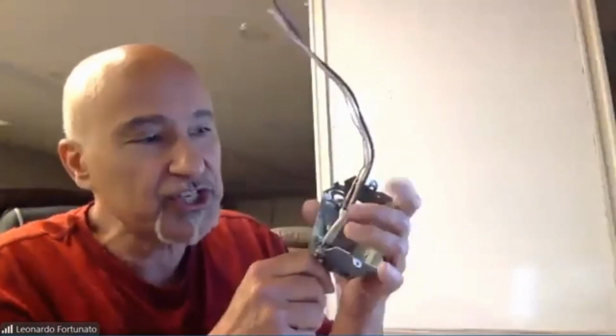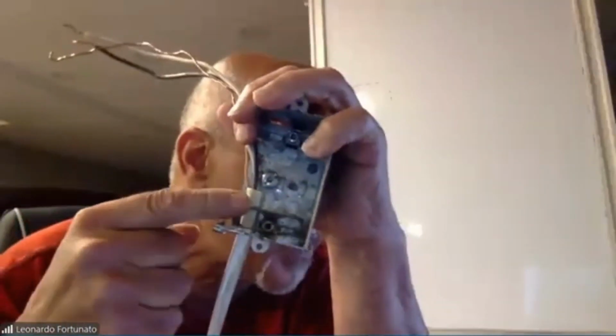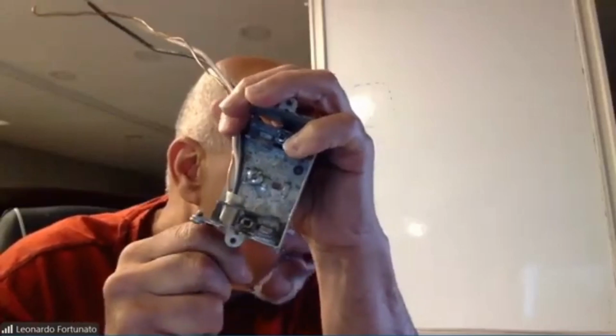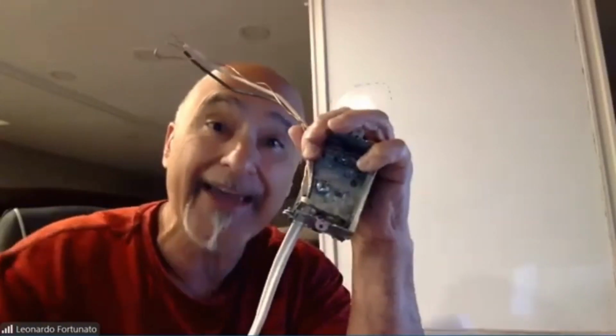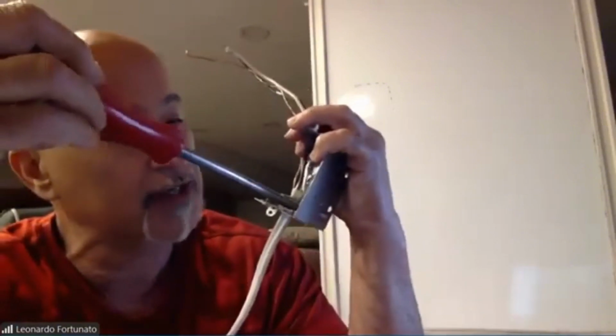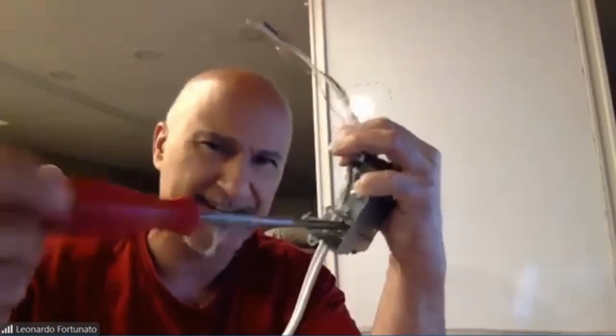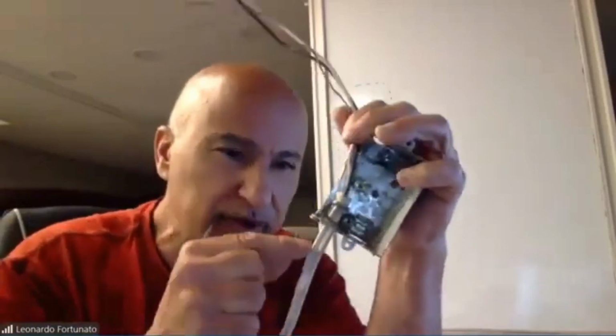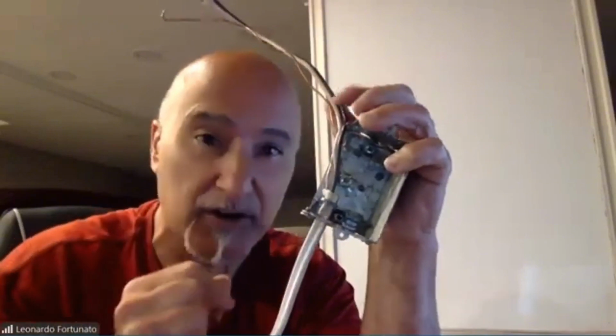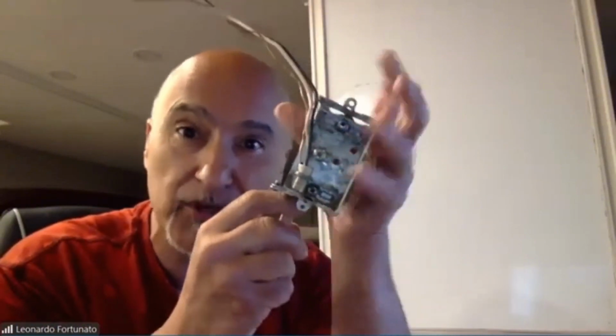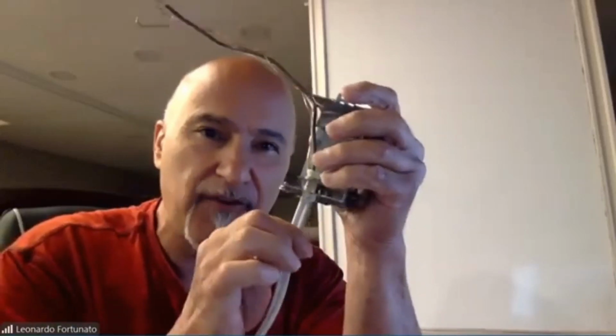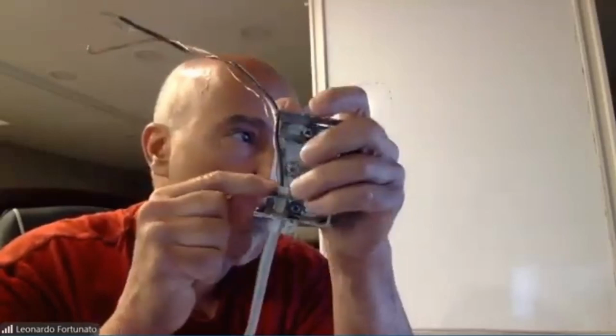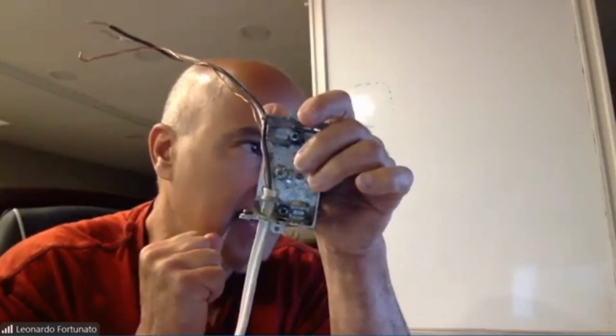Instead, you want the sheathing to just pass this bracket, this clip at the bottom. We want the sheathing to just clear that bracket, so that when I secure it, the wire won't come loose in the box. There's no need to over-tighten this screw — if you over-tighten it, you risk damaging the conductors that the sheathing is there to protect. We just want to secure the bracket tight enough that the wire won't pull out of the box, with the sheathing coming just past the clip.